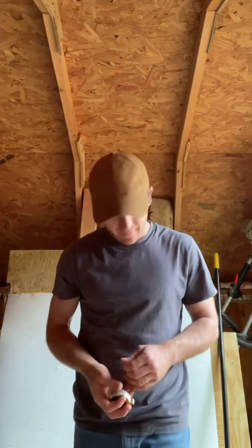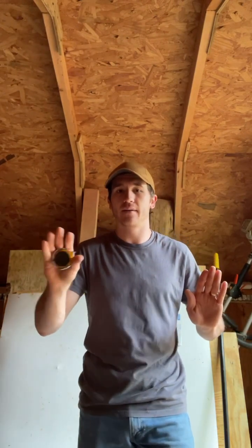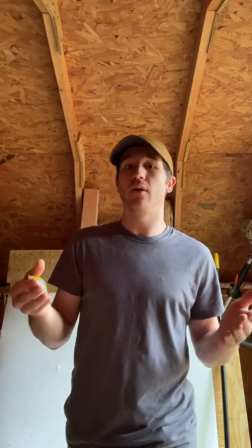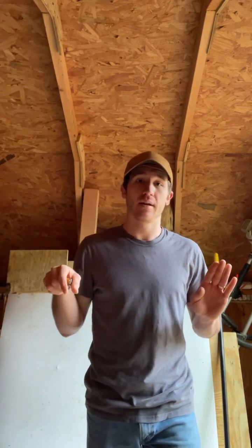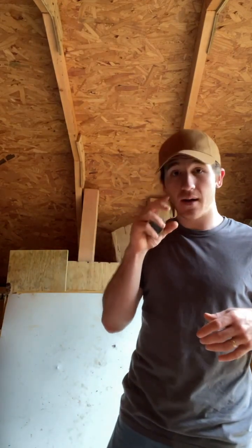Now if it's not the breaker and everything's sending out power, you can start looking for that break. So you've got power at your panel but no power in, say, your master bedroom, which means there's a break somewhere between A and B. You've got a wire going from A to B, then C is out and the rest of the room is out. You've got to find that place where it's not sending power, whether that's a receptacle outlet, a lighting outlet, or a junction box.